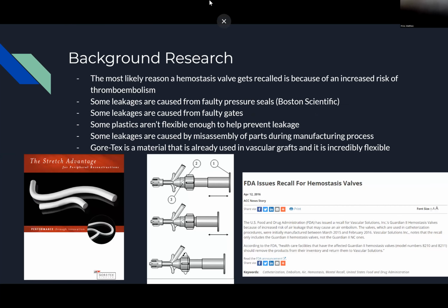It's also our responsibility to research some problems with current hemostasis valves. The most likely reason for a hemostasis valve to get recalled is because of the increased risk of thromboembolism. Pretty much the reason why we have them, so that's not a good thing. Some of these leakages are actually caused from faulty pressure seals, as in the Boston Scientific Guardian 2. Some leakages are caused from faulty gates. Some plastics aren't flexible enough to fully prevent the leakage. Some leakages are caused by misassembly of parts during the manufacturing process when there are multiple parts to be put together.